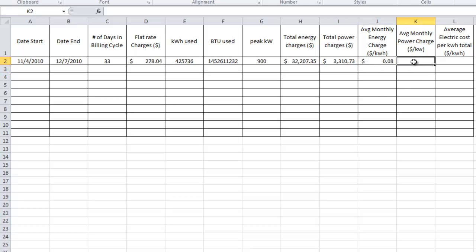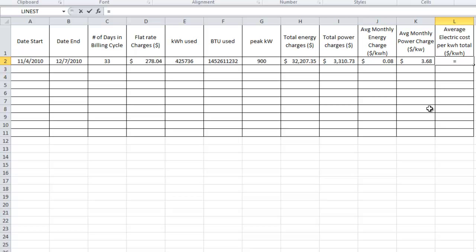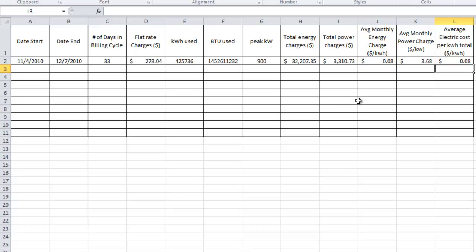Now let's look at the average monthly power charge — that's dollars per kilowatt. We take the power charges divided by the peak kilowatts, which gives us $3.68. Then, for the average electric cost per kilowatt hour total, I want the total cost of the bill: flat rate charges plus energy charges plus total power charges. This gives us an idea of the total cost of the bill per each kilowatt hour. If your power charges aren't that much, it will be similar to the energy charge; but if power charges are significant, this may be drastically different from your average monthly energy charge.